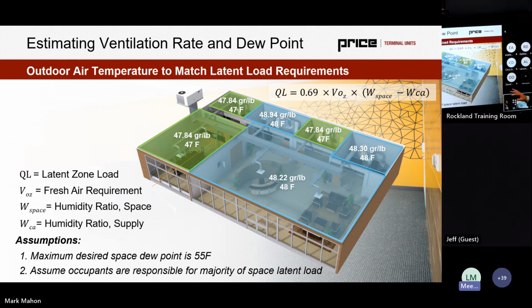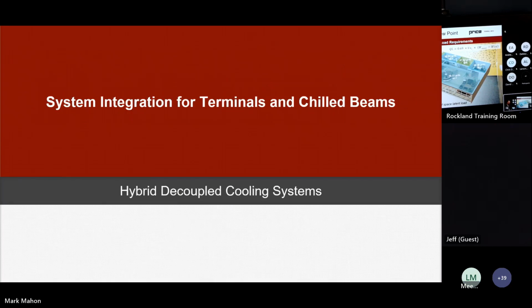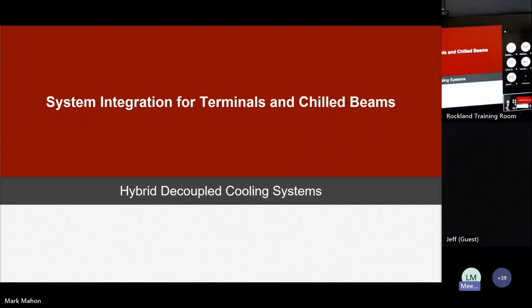So similar in this exercise, you'd go zone by zone, look at the worst case one, and we would set our supply air temperature from our DOAS air handler to that point, and that's what's going to provide our latent cooling. I apologize for all the math. Any questions on that? I promise we talk a little bit more about product and philosophy and theory moving forward here.